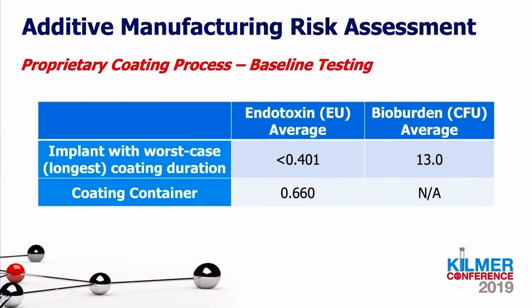So we did some testing, and we found that the implants that were subjected to our worst case coating process, which is the longest coating process that we could possibly use, had endotoxin below the limit of detection, which made us very happy. And the bioburden average was also very low. The coating container was also tested, and a value of 0.66 EU per container is very low.